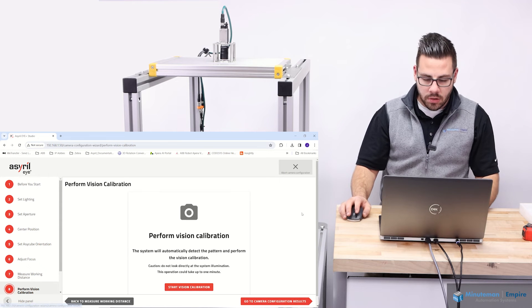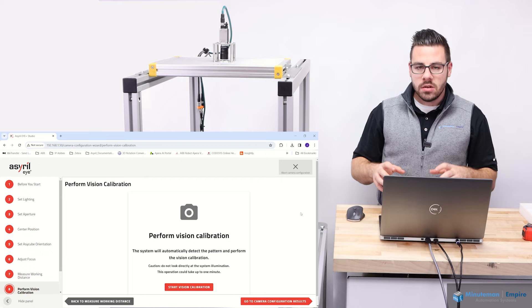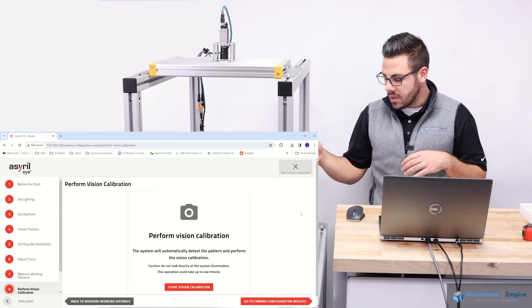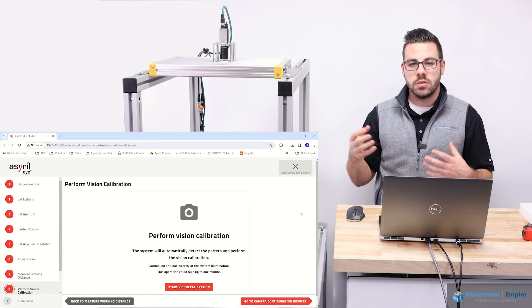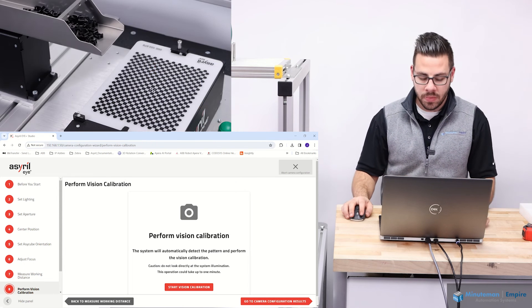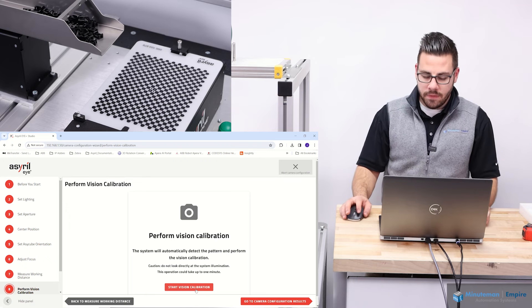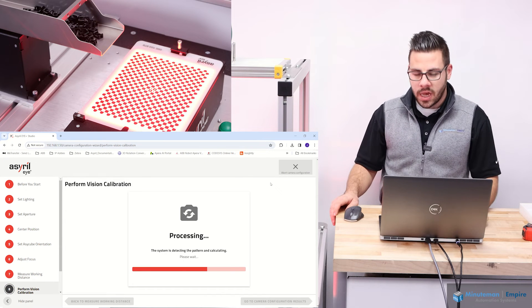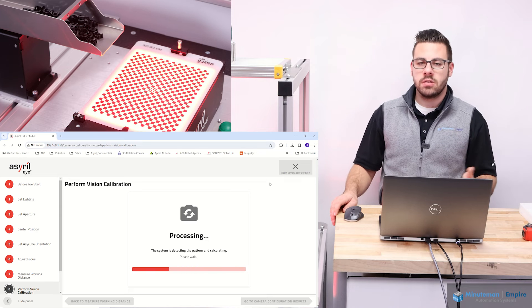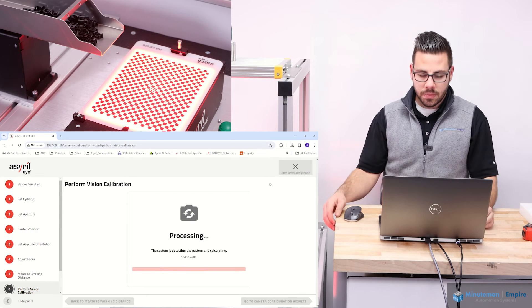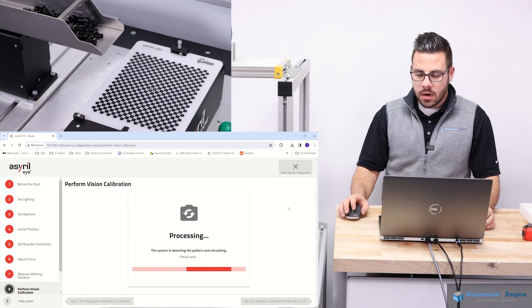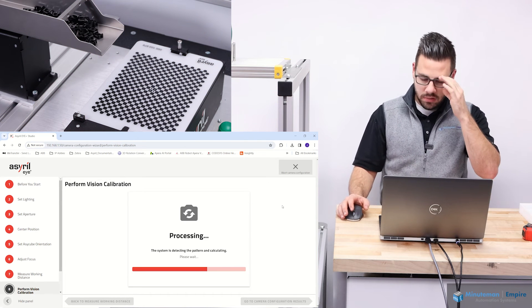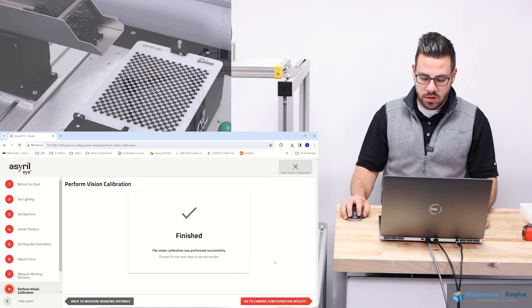Then we're going to go to perform vision calibration. The system knows inherently what the distance between each of those checkerboards is on the plate itself. So it's going to use that to get a pixel to millimeter ratio. If I click start vision calibration, you'll see the system is going to go through, take a couple images, do some image processing to really find that pattern on the plate. If it's successful, we'll get some data feedback here. So it's not a long process. Should be wrapped up here in just a second. And yep, we are finished.